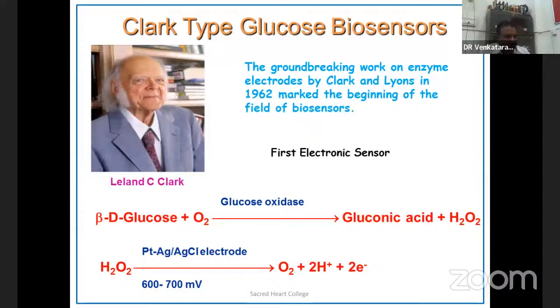Here, the molecule gluconic acid will not undergo an oxidation or redox process at or below a potential of 700, but hydrogen peroxide is electroactive at this potential, and it is monitored at a platinum electrode, on top of which your glucose oxidase can be interacting. That means the reaction between the glucose and glucose oxidase is sensed by the platinum electrode by analyzing the hydrogen peroxide concentration at an applied potential of 600 to 700 millivolts.